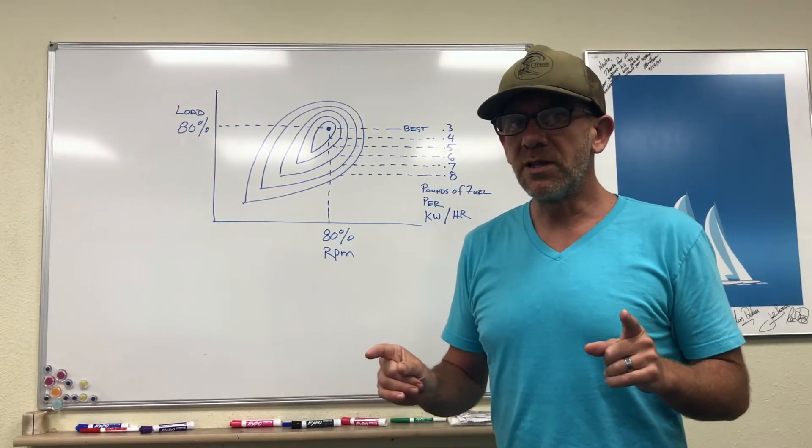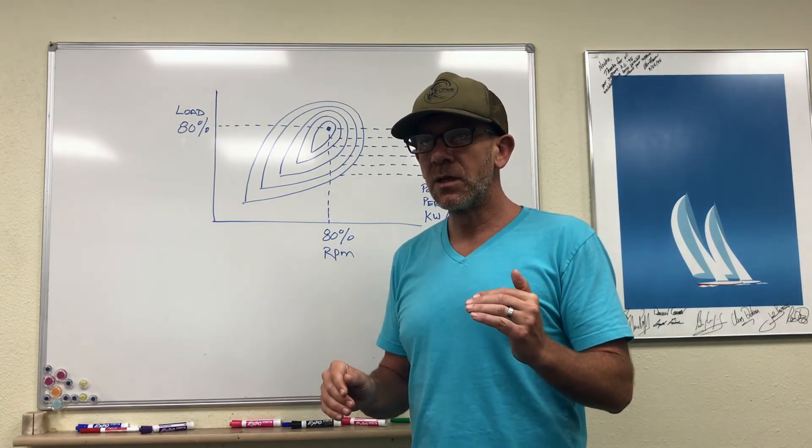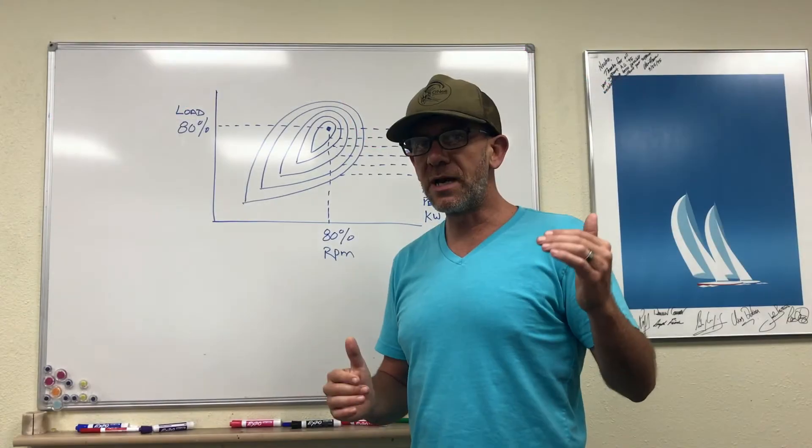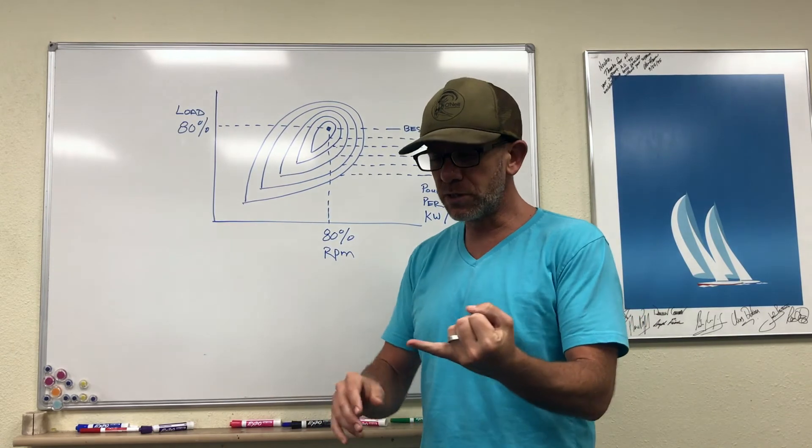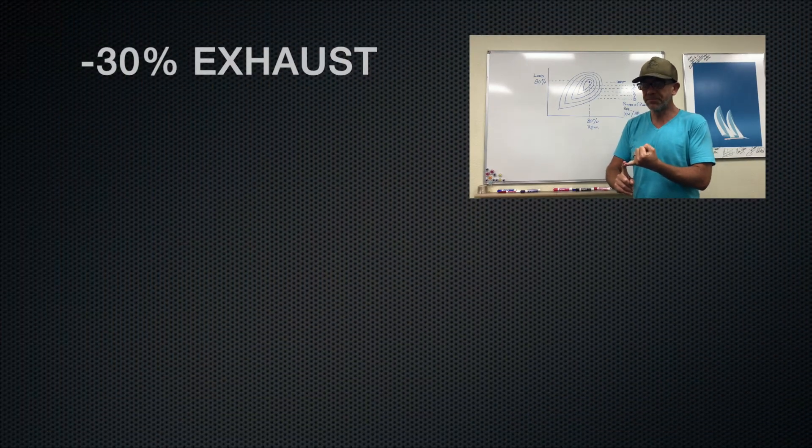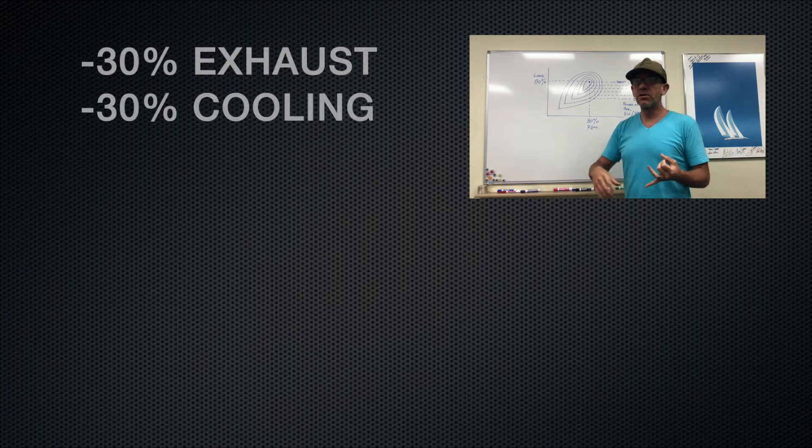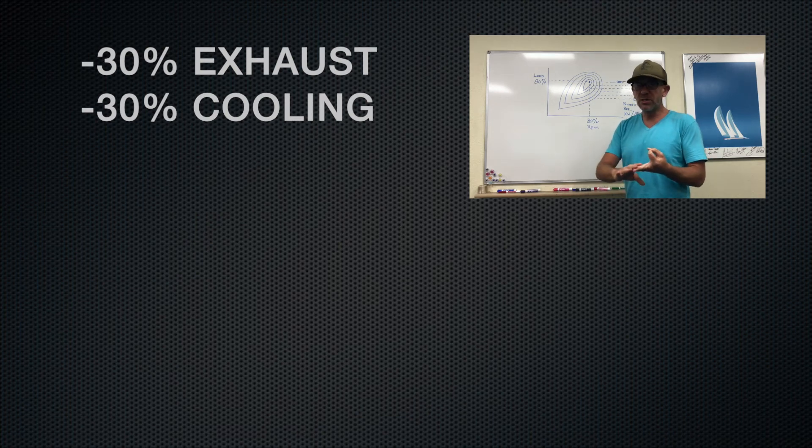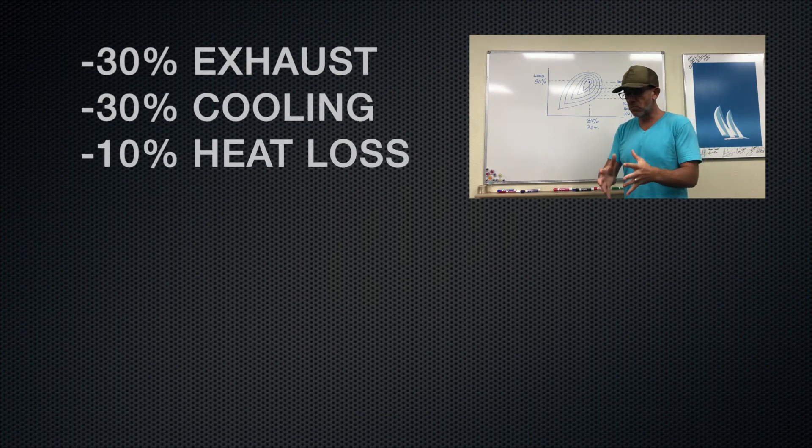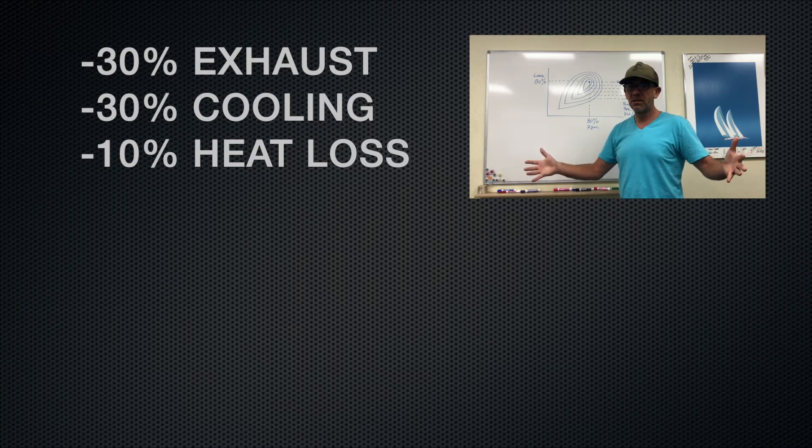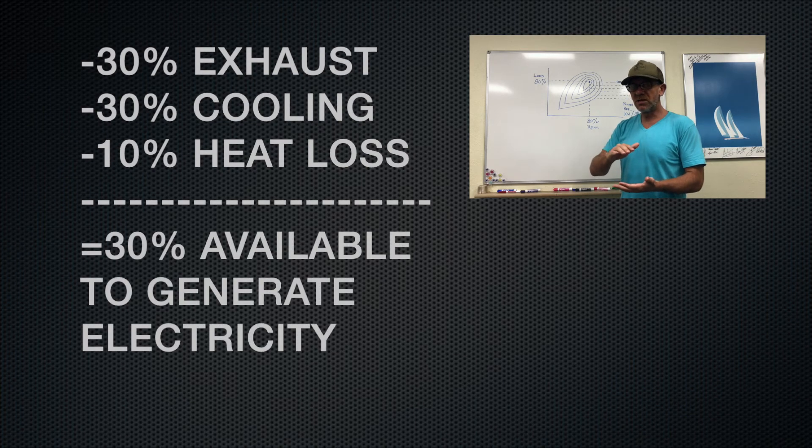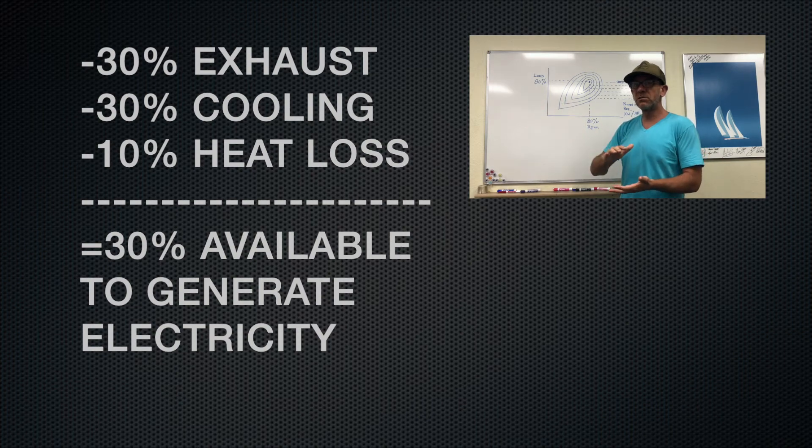Now when you run that fuel through a diesel motor, diesel motors have considerable parasitic losses. Those parasitic losses will detract from the overall power. So you're going to spend roughly 30% of the energy going out the exhaust pipe. Another 30% is going to go through the cooling system, and then you're going to lose another about 10% of just radiated heat coming off of the block.